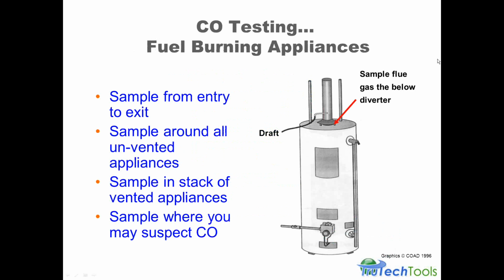When we're doing a CO test on a fuel burning appliance, the point of this graphic is to illustrate that we do want to sample from entry to exit. That means from coming into the structure until we leave. We do want to sample around all unvented appliances, because their effluent or flue gas products are coming right into the room, being contained in the structure and not leaving through a vent system. And then you want to check around the stack of vented appliances, because that's where the reversals or problems with insufficient dilution air can cause your vent not to operate properly and to cause CO production, and anywhere else you might suspect CO taking place.